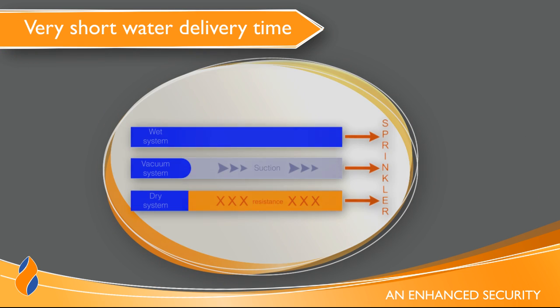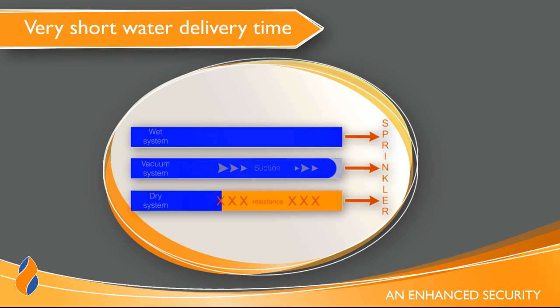In a wet system, during a fire and as soon as the fuse is broken, water flows immediately on fire if there is no sealing or clogging. In a dry system, water arrives after total evacuation of the compressed air within pipes. Unlike the vacuum system, wherein water is sucked by residual vacuum, which does reduce the delay.